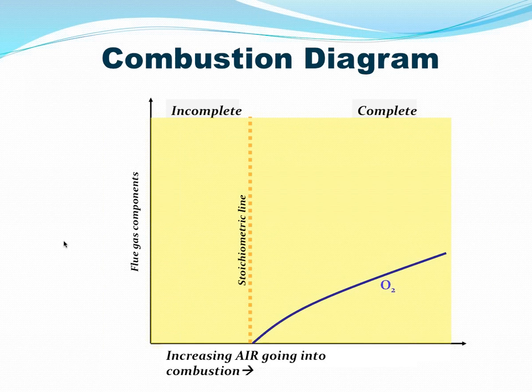Here's the line of increasing oxygen. This is basically what would be happening to your meter if we were able to dial in and change things, either the amount of fuel or the amount of oxygen going into combustion, so you'd get variable conditions. So what would it look like if we were changing the amount of air going into combustion? The interesting thing you'll notice here, or at least I think it's interesting, is that oxygen starts out at zero at the stoichiometric line. We're getting no residual oxygen being measured by the combustion analyzer because there's not enough to go around. There's too much fuel for the oxygen available, so it's all getting used up. Beyond the stoichiometric line, there's enough extra oxygen left over that you can start to detect and measure it. That's why oxygen rises when you're on the right side, the complete combustion side of the stoichiometric line.